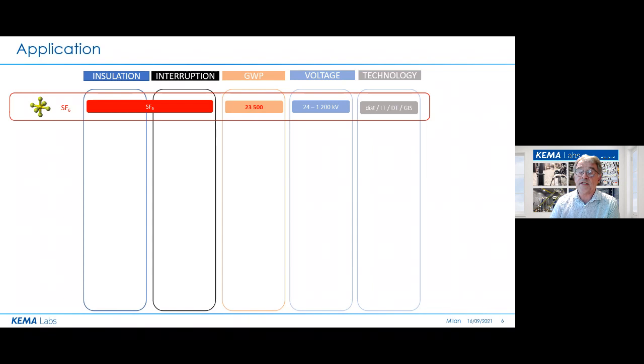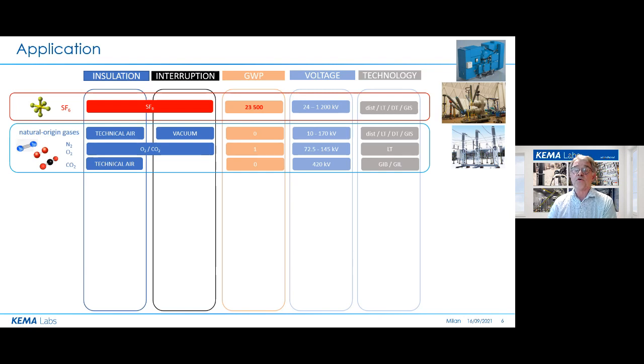Well, its bad side, of course, is its GWP, and it is really only because of this that many wish to say farewell to SF6. Well, then again, the oldest alternative, with only natural origin gases around, most common is switching in a vacuum environment and insulation with compressed air. Replacement of SF6 by natural origin gas is a natural development step because high voltage vacuum air insulated switchgear has been in use for 20 years. For very cold locations, O2, CO2 live tank switchgear has been developed some 10 years ago as well. Also in this live tank application case, the natural origin gas breaks and insulates.